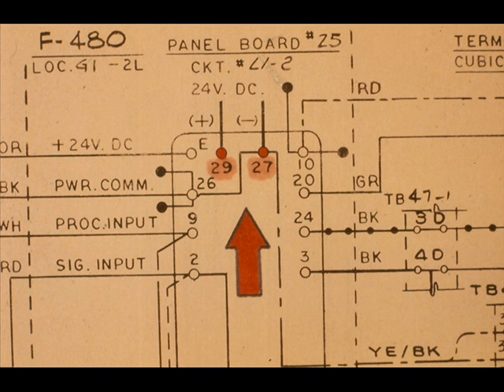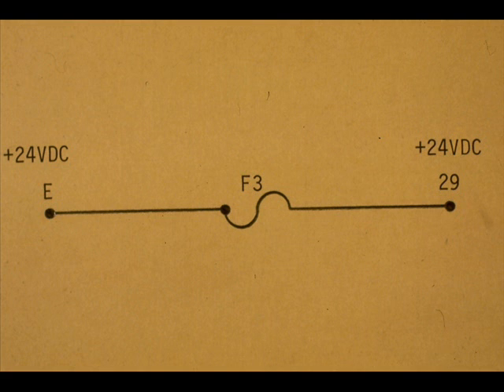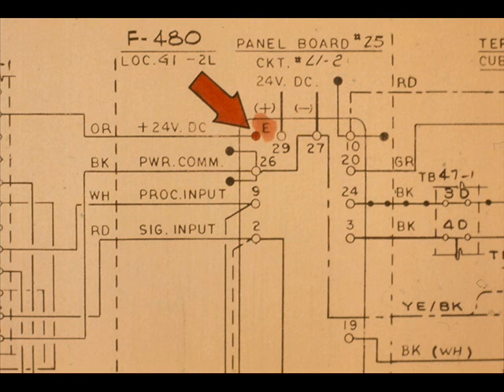Locate terminals 29 and 27 on the loop diagram. Controller terminal E is powered with 24 volts DC through fuse number 3. Notice terminal E.